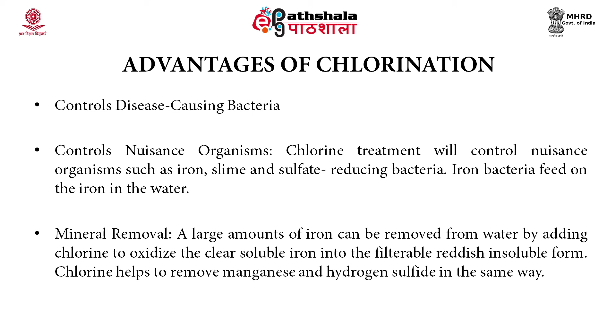and this chlorine treatment will also control the concentration of iron, slime and sulfate reducing bacteria. A large amount of iron can be removed from the water by adding chlorine to oxidize the clear soluble iron into the filterable ferric form of the iron, which is insoluble. Chlorine helps to remove manganese and hydrogen sulfide also from the water in the same way.